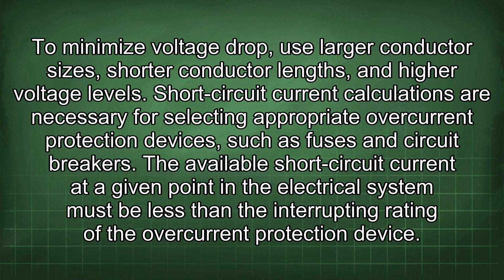Short circuit current calculations are necessary for selecting appropriate overcurrent protection devices, such as fuses and circuit breakers. The available short circuit current at a given point in the electrical system must be less than the interrupting rating of the overcurrent protection device.